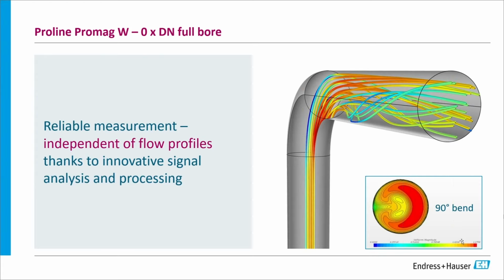So to get into this a little bit, one of the biggest challenges of flow measurement technology is generally the installation and the straight pipe requirements that are required to get an accurate flow meter reading. Typically for magnetic flow meters, the industry standard is to require 5 times the diameter of the pipe in straight run before and 2 times the diameter of the pipe after the meter to ensure laminar flow so that we can get an accurate measurement.